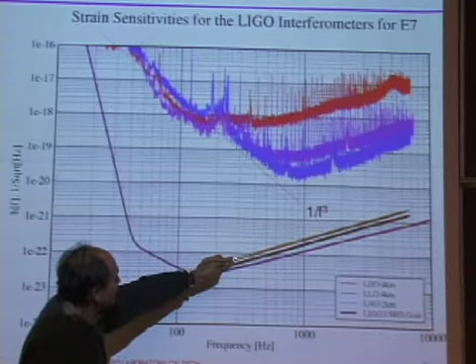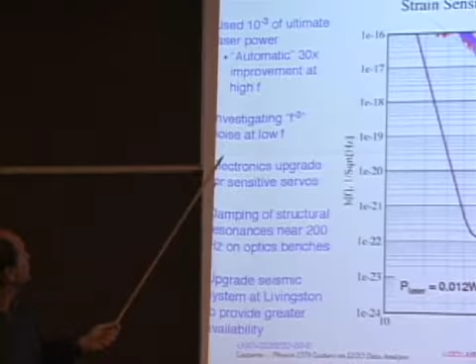So the expectation is that the curves at the high frequencies will come down and approach, as expected, the design sensitivity. It's interesting that we have what appears to be a 1 over f cubed limiting noise at low frequency, and that's currently clearly instrumental in nature, not intrinsically related to the seismic wall that is expected to produce this limit. And that's currently an active area of investigation by the commissioning team to understand what's the cause of this 1 over f cubed noise behavior at low frequencies.